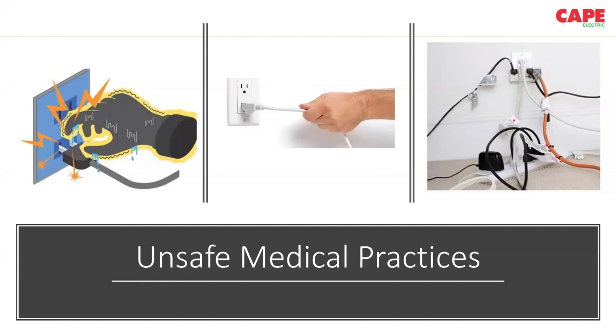Or connecting multiple equipments to an extension cord. Remember, sometimes this extension box would also be a locally made one, not a standard one, or not up to the standards, used without the fuse and all. What happens is that it gets overloaded. At that time, a short circuit or an arc, anything can happen. The probability of an electrical hazard at that time is very high. Or it can be due to a faulty equipment. The faulty equipment can be connected to the electrical connection, or it can be connected to a patient also. In both conditions, patient safety is a problem.